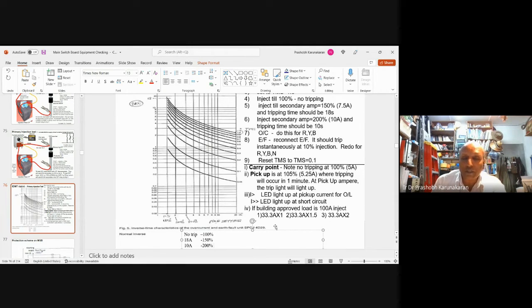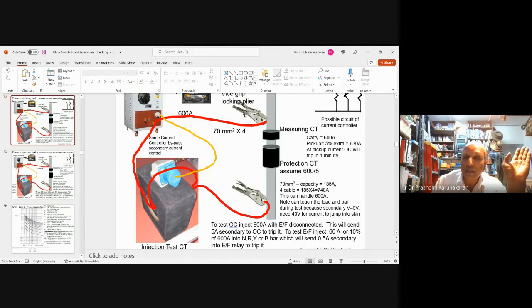Sorry for the confusion. So let me repeat again. When you inject like this, if you inject 100 amp, that means 100% of your CT incoming. CT incoming is say 200/5. You put 200, that means 100%. If you inject 200 amp, it should not trip. Make it 100, make it easy. Make it 100 amp.